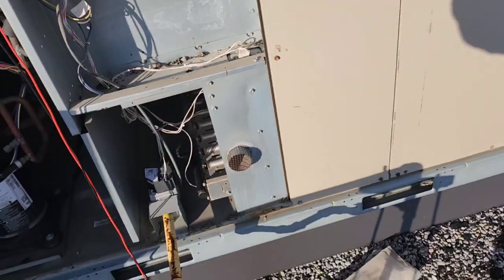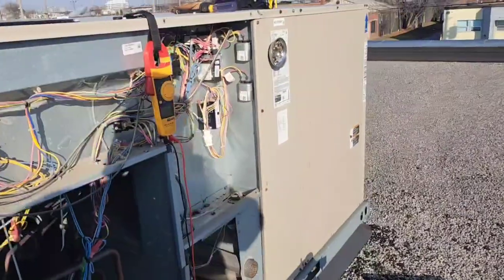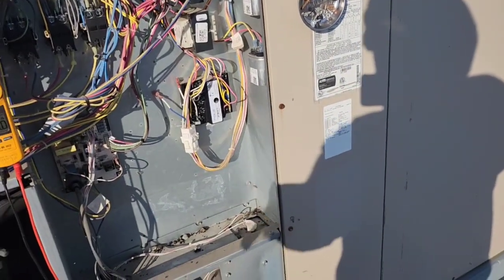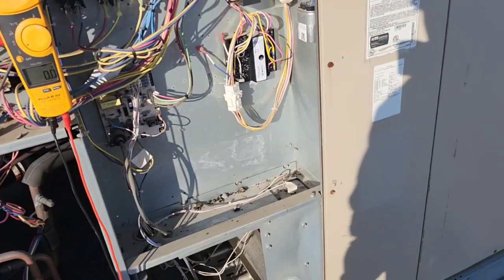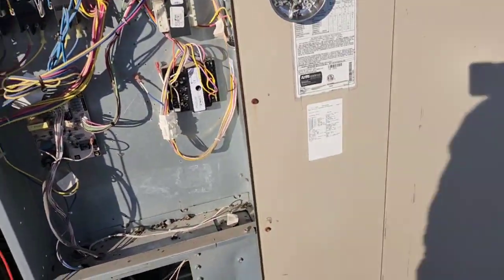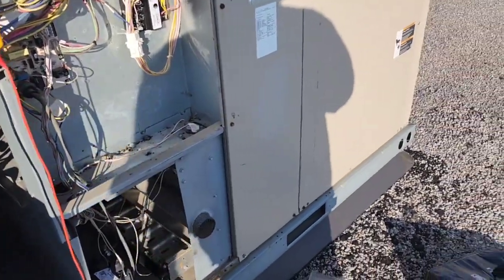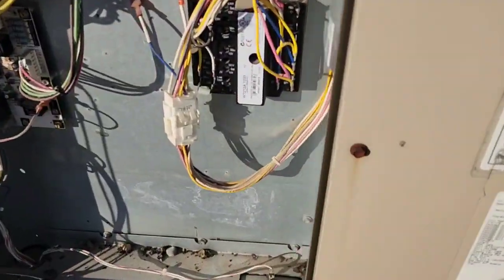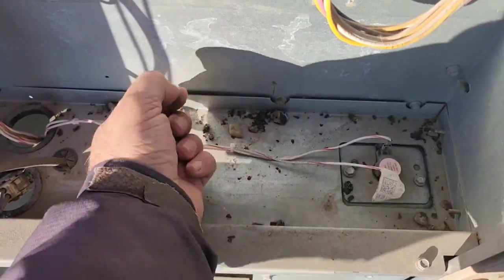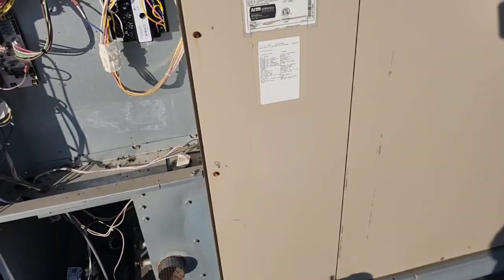At this point I'm going to go get a new filter — just regular maintenance. None of these companies, they should know better. This unit should be maintained. Somebody should come up here and change the filters twice a year, maybe three times preferably. Look at this — it's terrible. Yeah, basically tripping on that high limit.